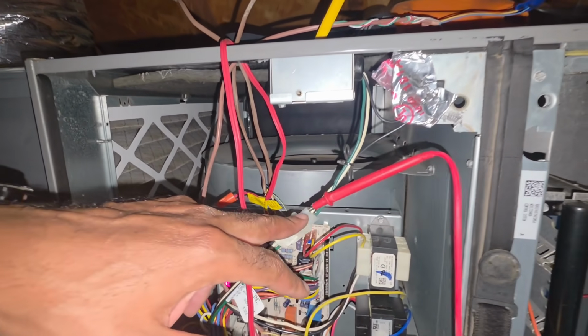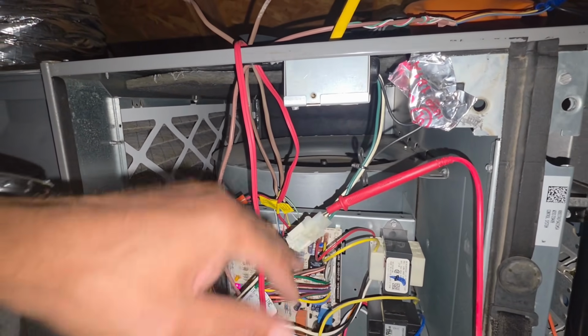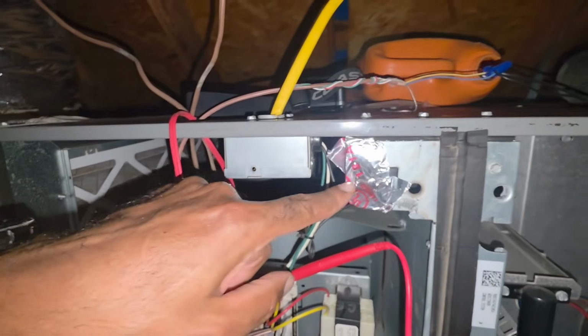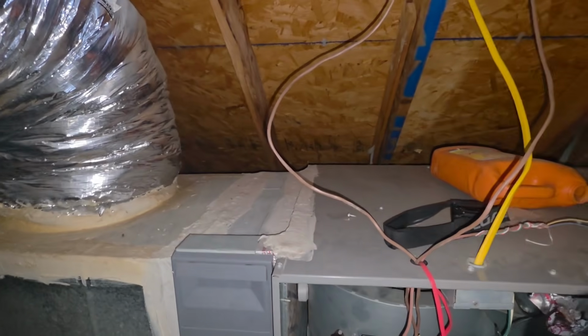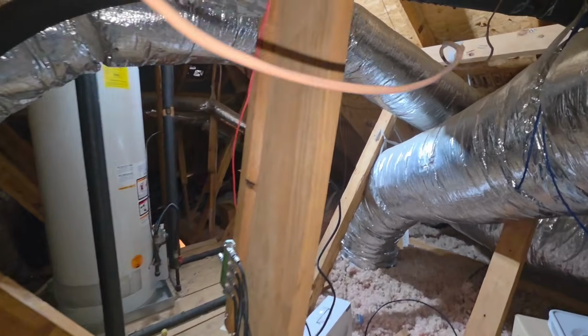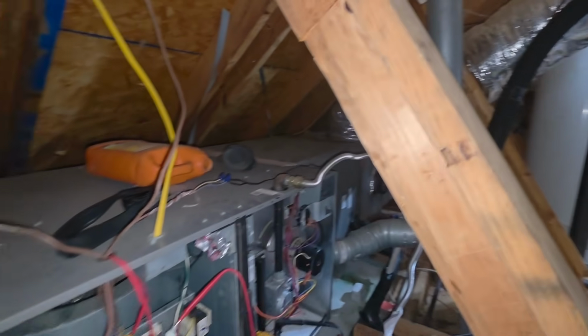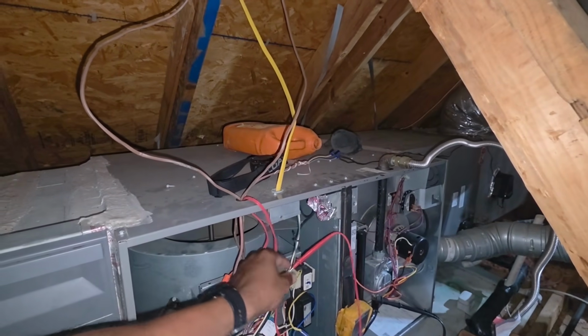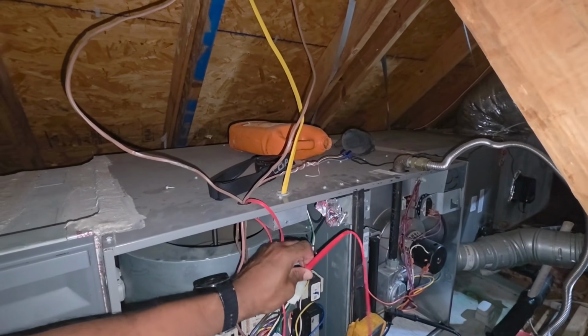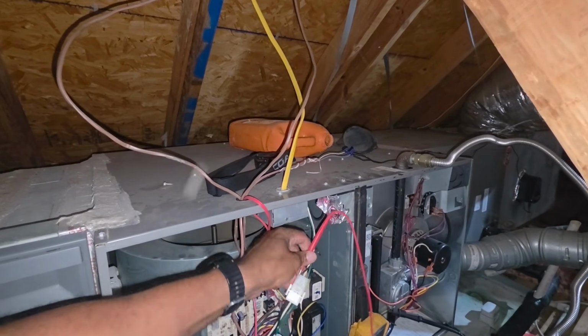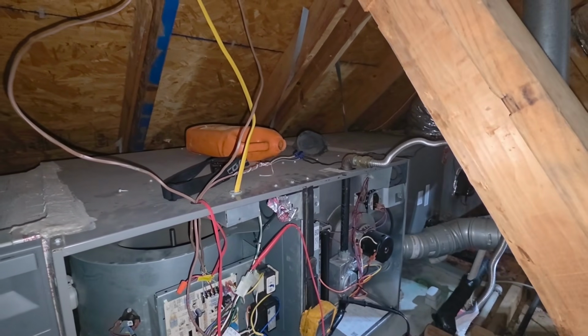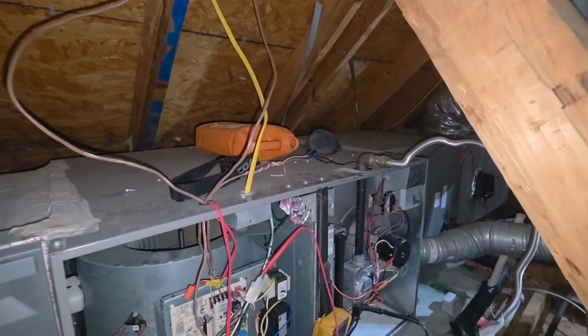Like I say, when you're doing the pivot method, we're trying to find out where we're losing voltage. If I'm getting 0 coming out of that door switch, that's when I know I got to kill my power. So if I was just troubleshooting that door switch or something, if I was getting 0, I would have to kill power and then come and troubleshoot this door switch by checking continuity. Well, that's another video.